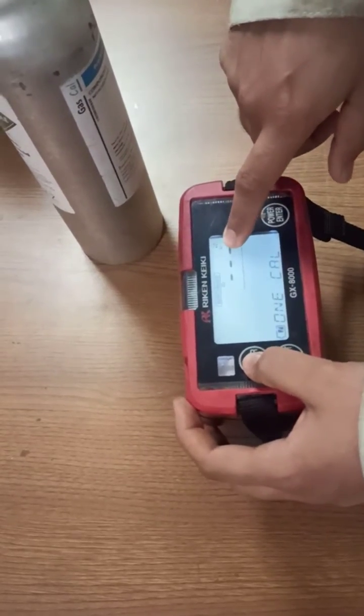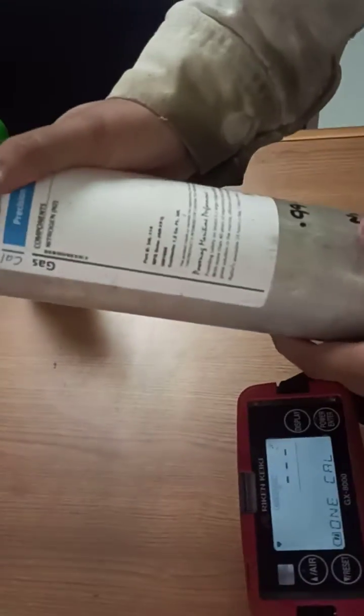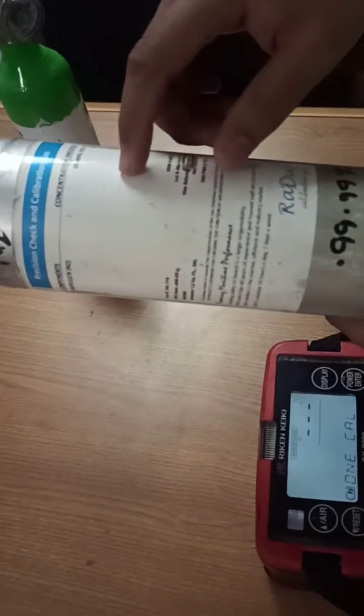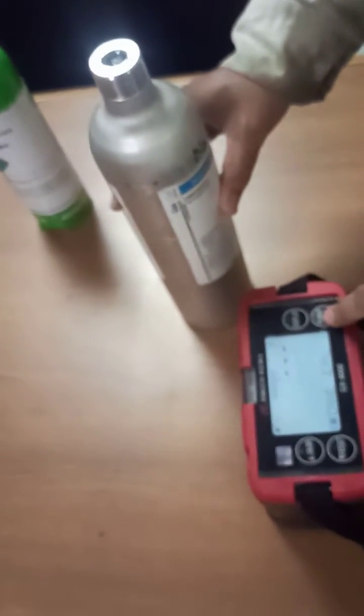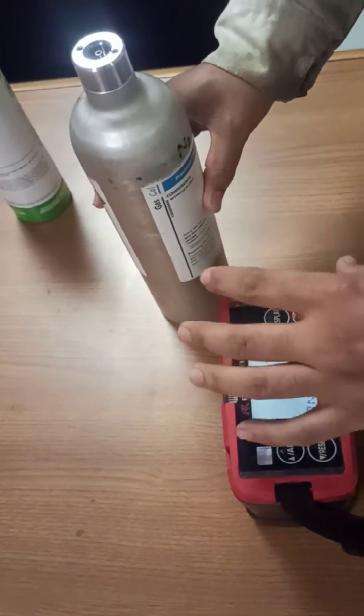O2 sensor is selected. After this, you have to take the nitrogen bottle. As shown, this bottle contains 99.999% volume concentration of N2. If we connect this bottle to the gas meter and do one cal, the O2 sensor will show zero oxygen, zero percent oxygen.